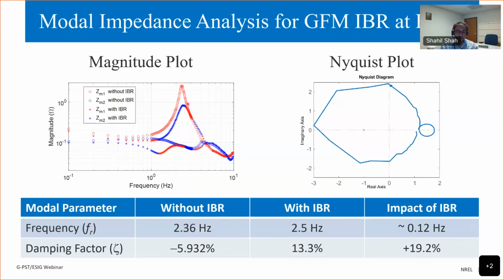Using these modal impedance responses, we see that with the IBR, the resonance is at 2.5 hertz, which is what we also observed in the time domain simulation. Without this plant at bus 6, the resonance mode is at 2.36 hertz. And as I said, looking at the Q factor, we can also find out the magnitude of damping. With IBR, the damping is 13.3%, and without IBR, it's minus 5.9%.